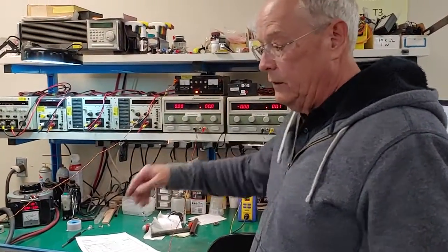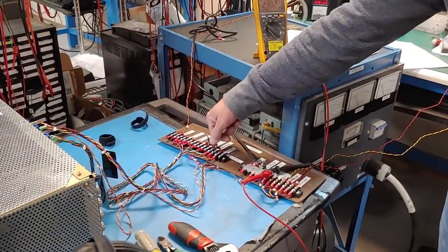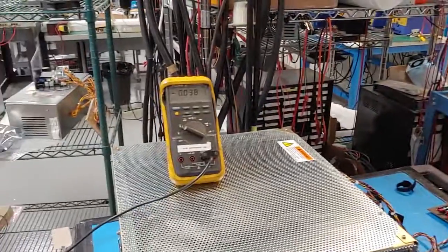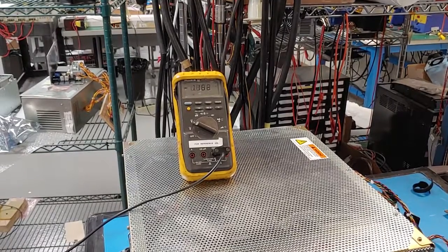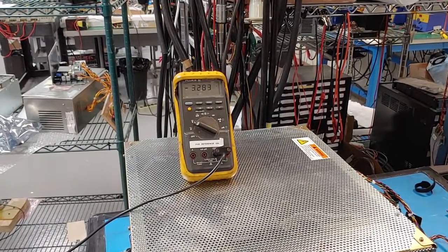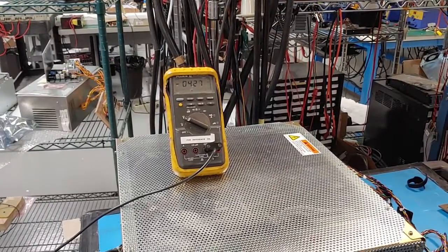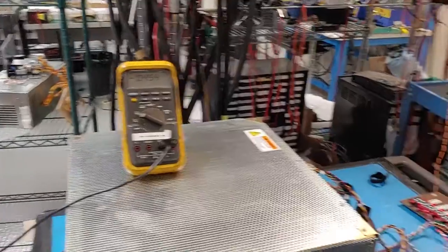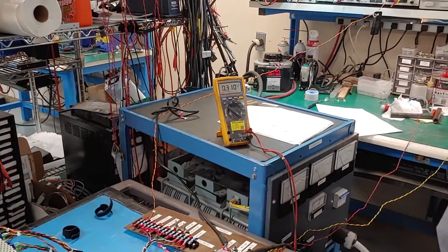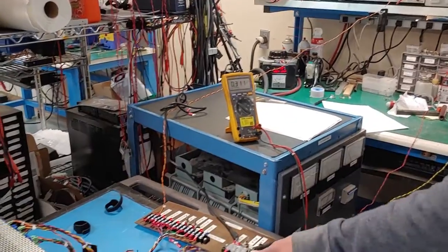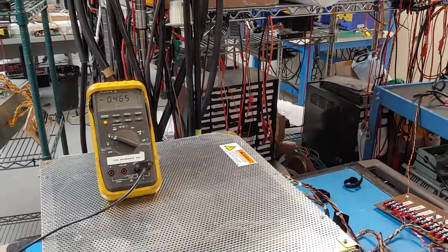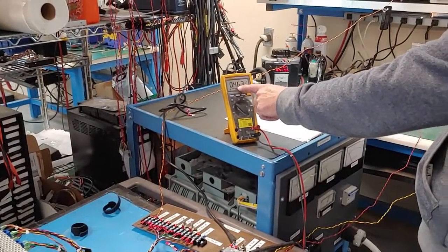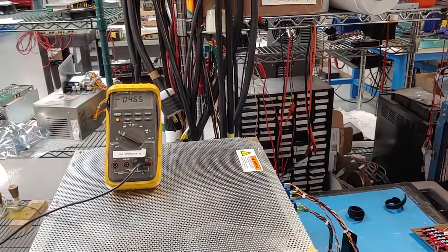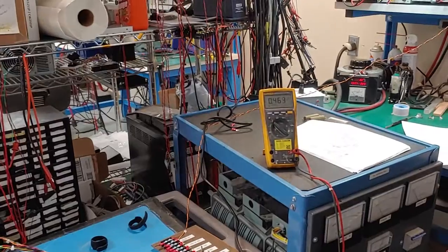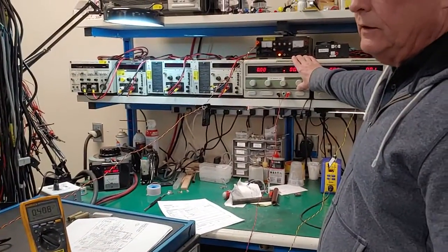So, to bring this up, we'll go ahead and turn on our current control and turn on our high voltage control. Over there, my high voltage will start to come up as I increase the power. There we go. So now that I'm increasing power, that's only about 4,000, 5,000. I'm going to go over and check my current monitor and make sure that I'm reasonable. That's great. I'm going to make sure my high voltage monitor is agreeing with my high voltage meter. There's my high voltage monitor at 263. 265 is the actual reading. That's well within tolerance. I mean 465 and 463. All right, so I'm going to go ahead and bring this up to 60,000.